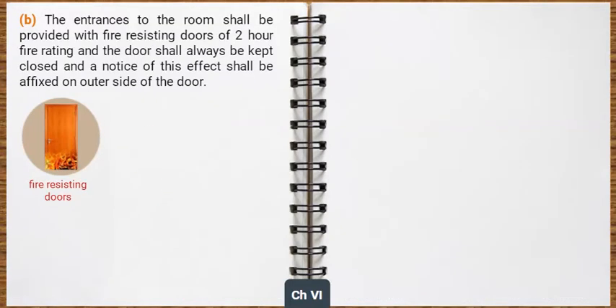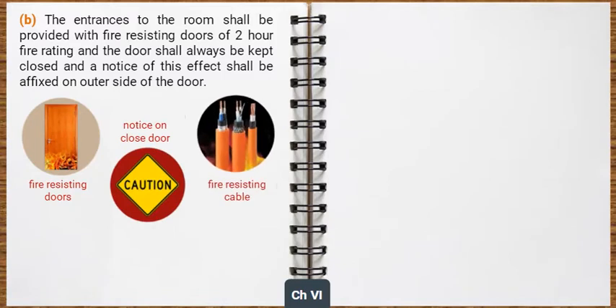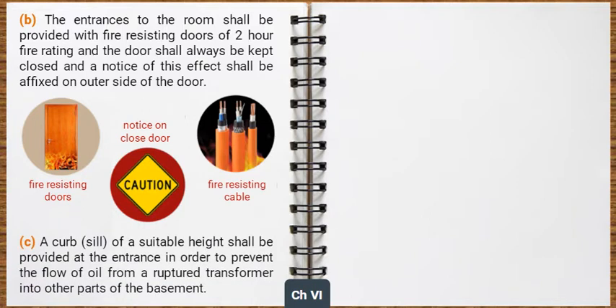The entrances to the room shall be provided with fire-resisting doors of 2-hour fire rating, and the door shall always be kept closed, and a notice to this effect shall be affixed on the outer side of the door. A curb sill of a suitable height shall be provided at the entrance in order to prevent the flow of oil from a ruptured transformer into the other parts of the basement.